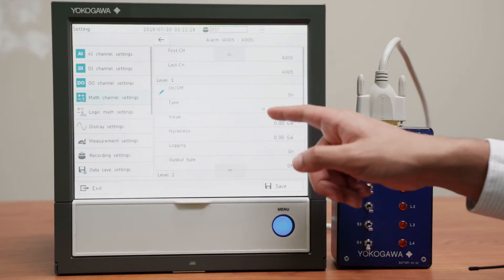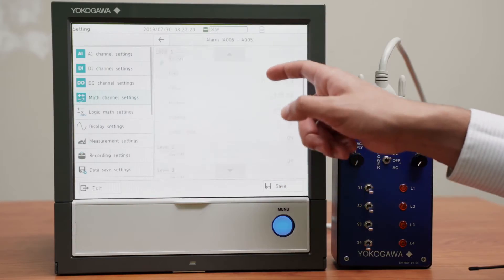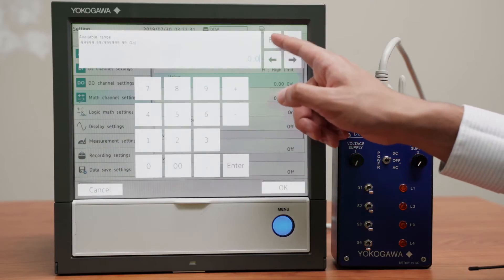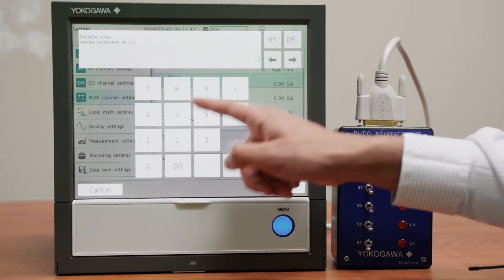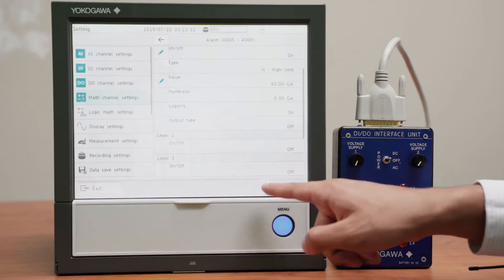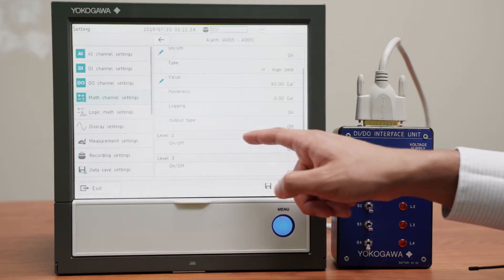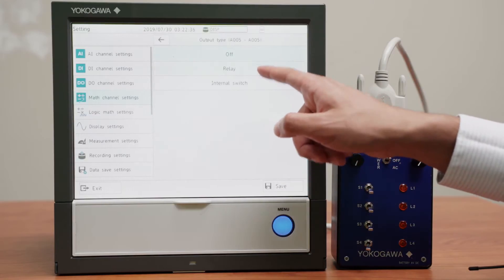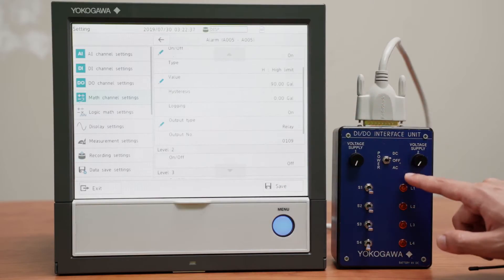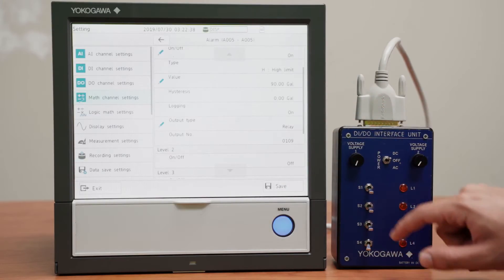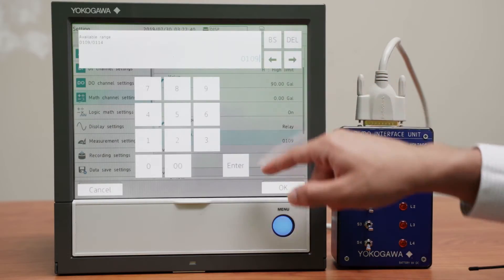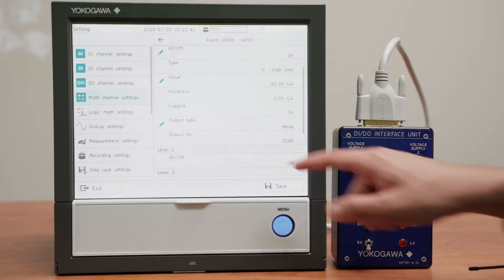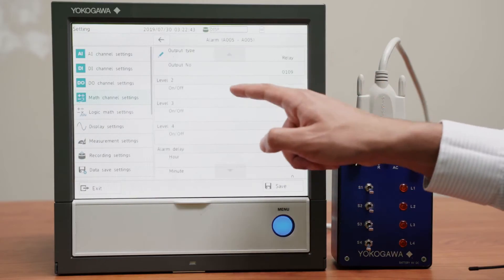So first, it's a high alarm, and I want that to turn on at 90 gallons. And I want the output type to be a relay, which makes it a digital output. Channel 109 is this one, that's fine.